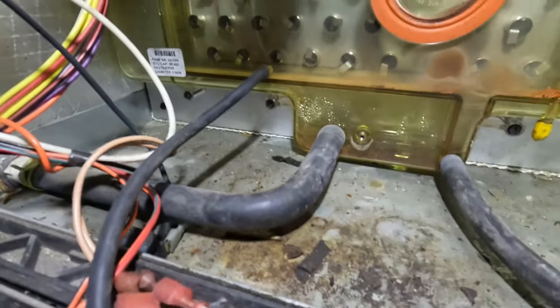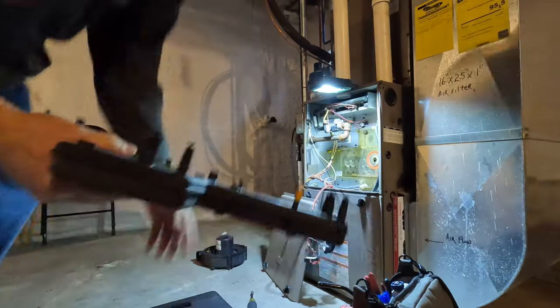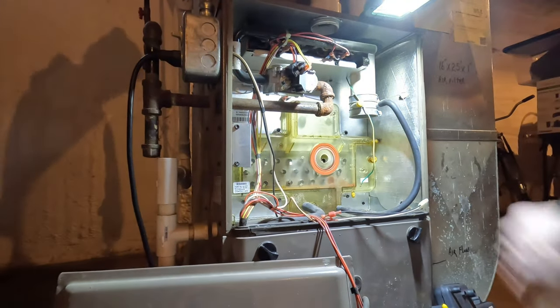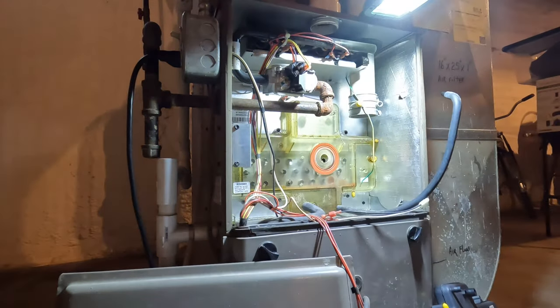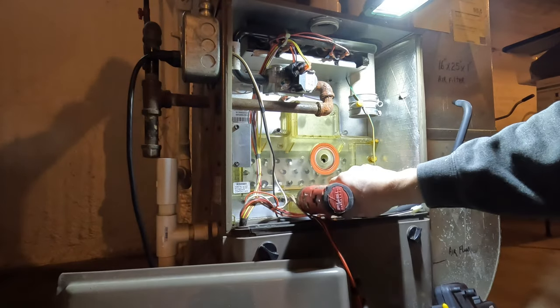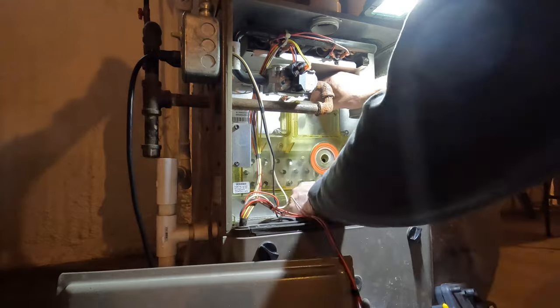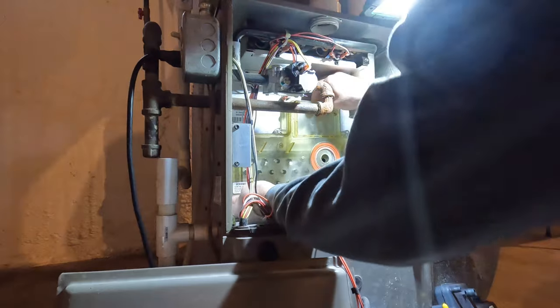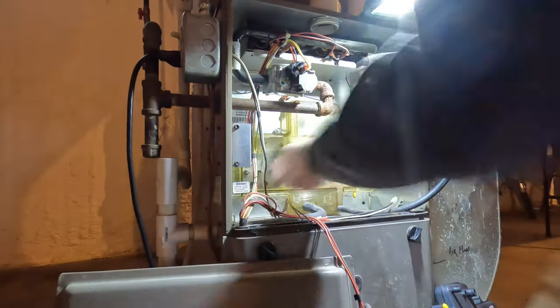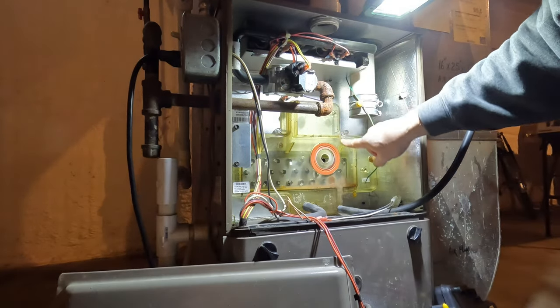See how it's pretty cool — you can see what's going on in there. It's kind of gunky at the bottom. Well, it is cracked right there. So I think we better replace it because it is cracked. Here's the new collector box. I'm going to take this off.